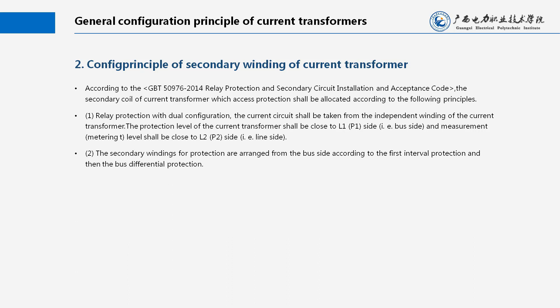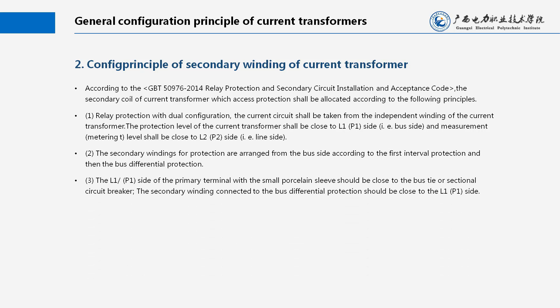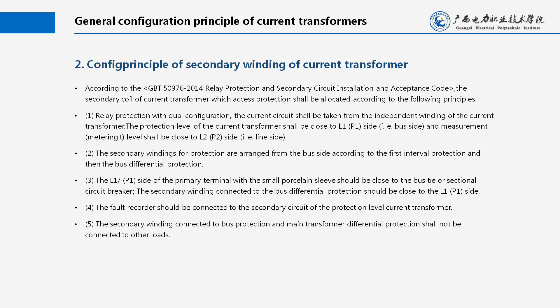2. The secondary windings for protection are arranged from the bus side, according to the first interval protection and then the bus differential protection. 3. The L1, P1 side of the primary terminal with the small porcelain sleeve should be close to the bus tie or sectional circuit breaker. The secondary winding connected to the bus differential protection should be close to the L1, P1 side. 4. The fault recorder should be connected to the secondary circuit of the protection level current transformer. 5. The secondary winding connected to bus protection and main transformer differential protection shall not be connected to other loads.